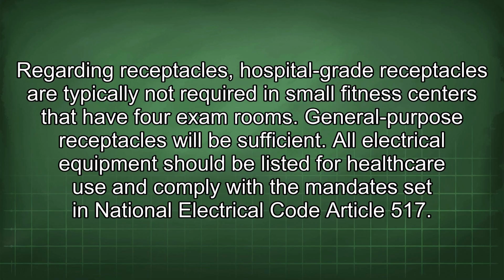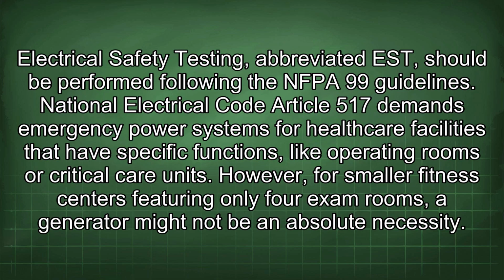All electrical equipment should be listed for healthcare use and comply with the mandates set in National Electrical Code Article 517. Electrical safety testing, abbreviated EST, should be performed following the NFPA 99 guidelines. National Electrical Code Article 517 demands emergency power systems for healthcare facilities that have specific functions, like operating rooms or critical care units.